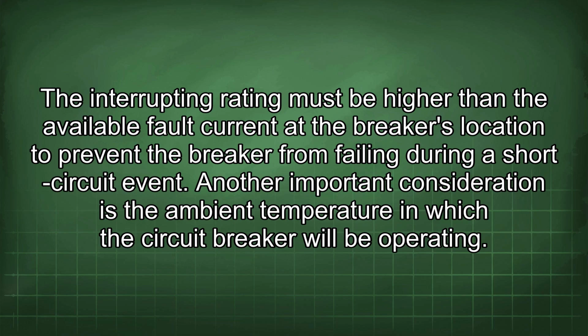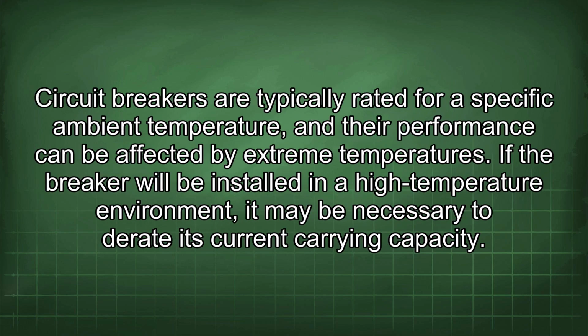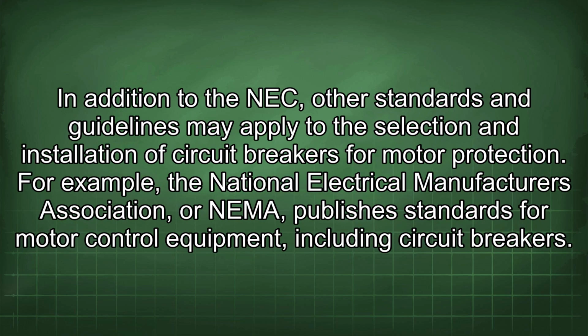Another important consideration is the ambient temperature in which the circuit breaker will be operating. Circuit breakers are typically rated for a specific ambient temperature, and their performance can be affected by extreme temperatures. If the breaker will be installed in a high-temperature environment, it may be necessary to derate its current carrying capacity.